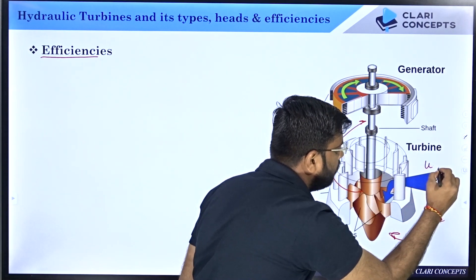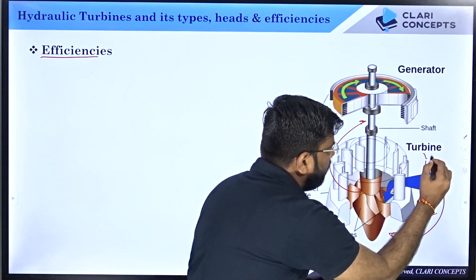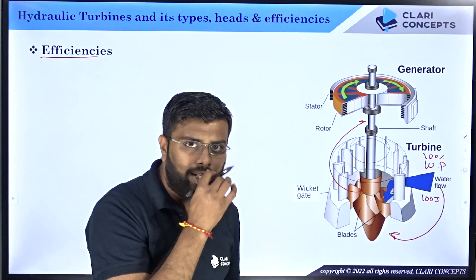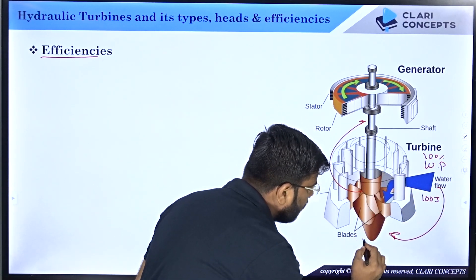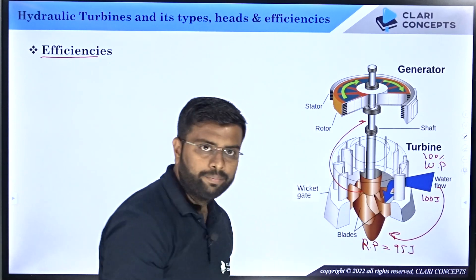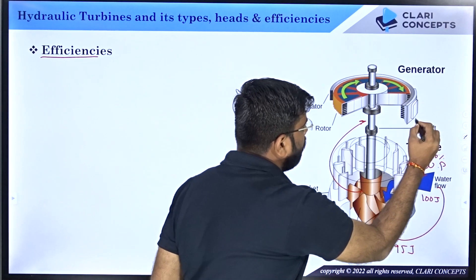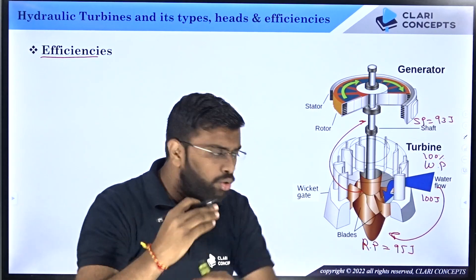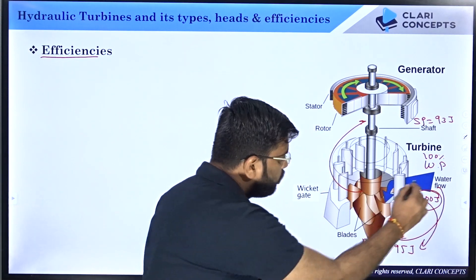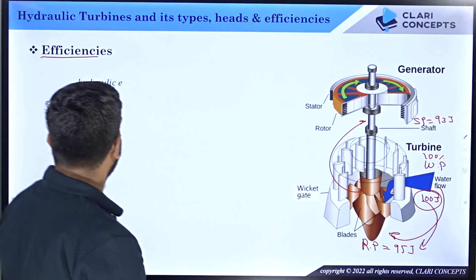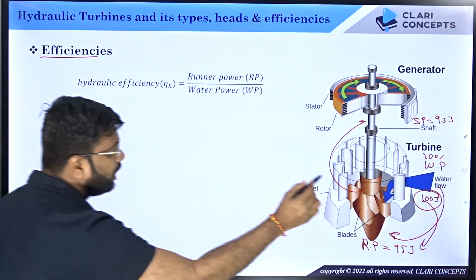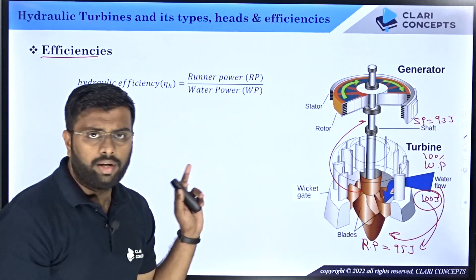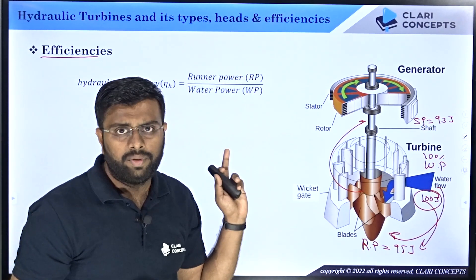The energy available in water is called water power WP. For example, say 100 joules. As the transfer is done from water to the runner, there is always a loss associated with any energy conversion. The energy at the runner we call runner power — for example 95 joules. Hydraulic efficiency eta_H is defined as runner power divided by water power, so 95 divided by 100 gives 95%. That is how hydraulic efficiency is defined — how much energy is transferred from the water to the runner.